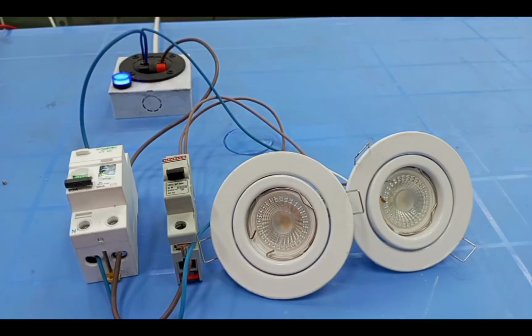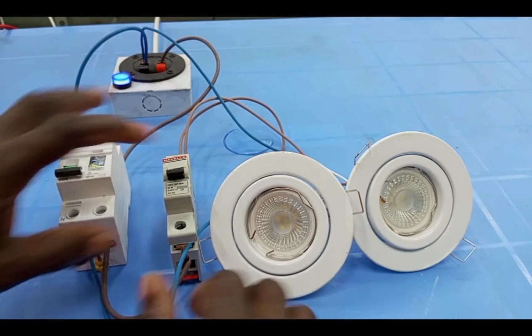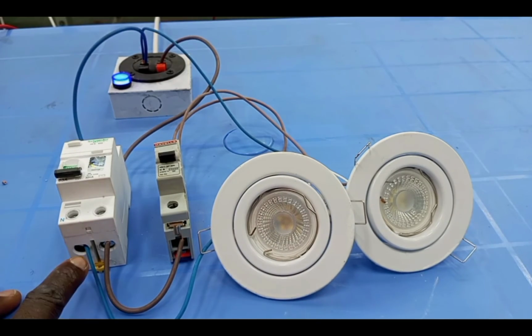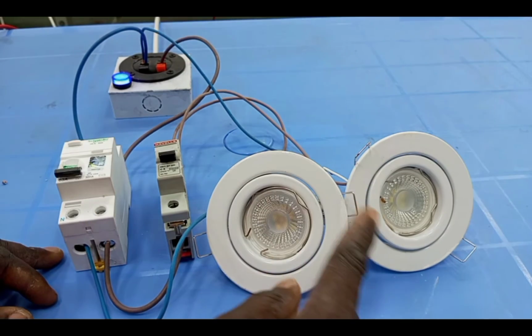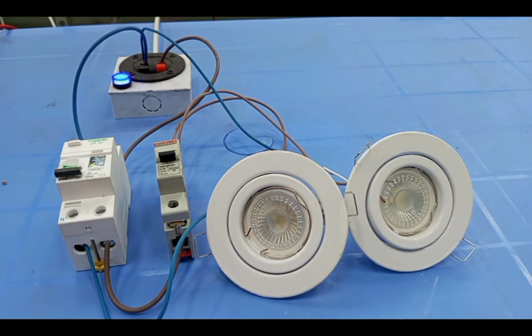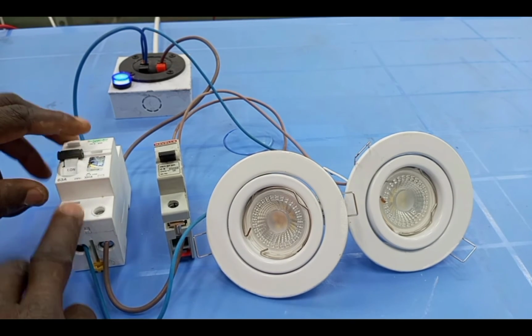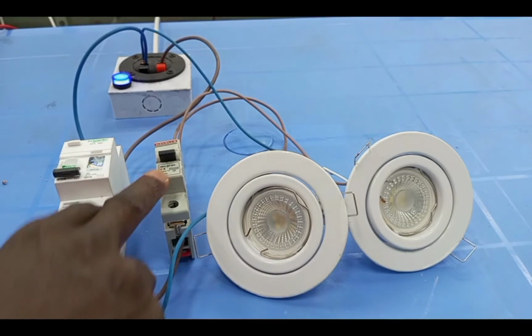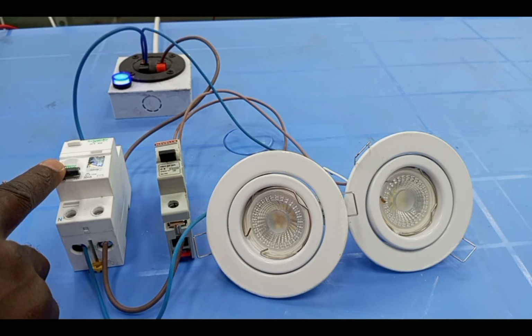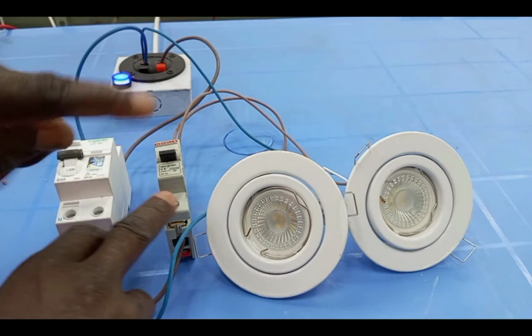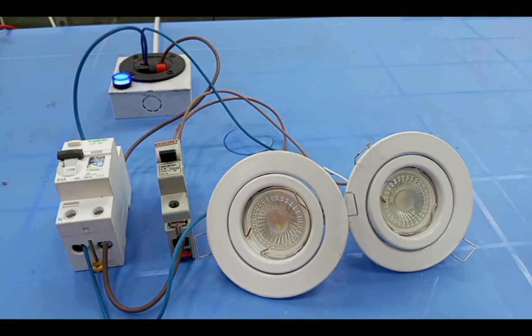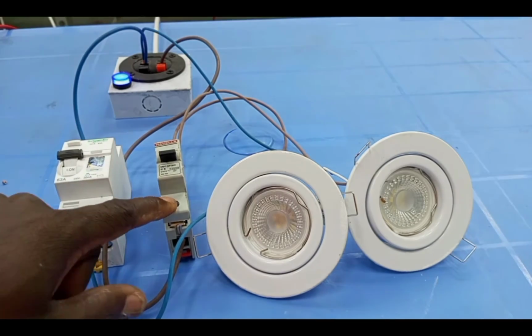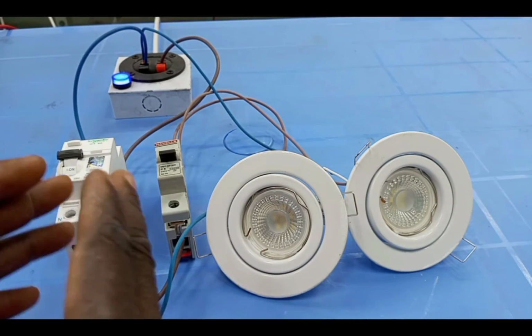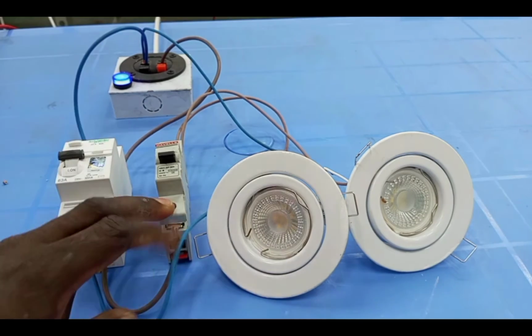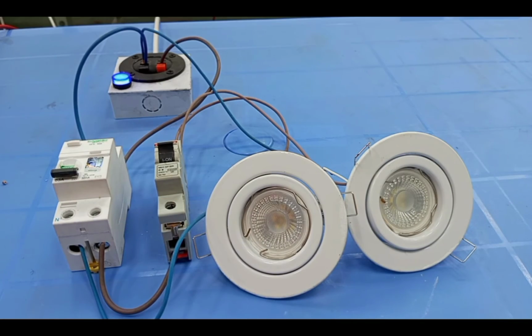Now, this neutral wire, I'll connect it to the main supply neutral wire here. All right, so now you see it is only one of the neutral wires that is passing through the RCD, but you have two live wires connected to two lamps. All right, so now when you switch this on, the RCD will trip. Look at it again. The moment I attempt to switch on the MCB, the RCD will sense the imbalance current. Quickly, it will go off. So that is how it works.